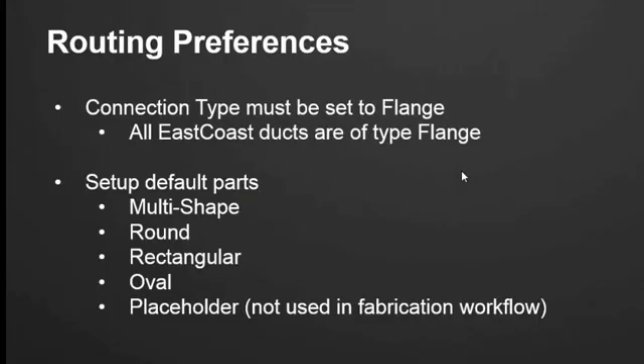Some things to make sure that happen inside the routing preference dialog is your connection type must always be set to flange. That's because all duct, whether it's round, oval, rectangular, or multi-shape, all of the East Coast duct is set to the AutoCAD MEP flange type, even if it does not have a flange. The reason being is that makes it easy for us to switch the flanges from slip and drive, TDC, maybe to a raw edge. The flange connector type in AutoCAD MEP is just a flag that's signifying that I can have a flange. It doesn't actually mean it has to have a flange.